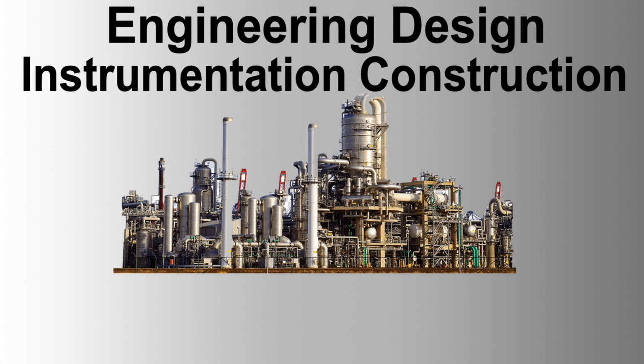Technical requirements. All instruments and their associated components shall be installed in accordance with all relevant drawings and data sheets. All instruments shall have individual connections to the process unless otherwise specified. No instrument shall be installed so that it depends for support upon the impulse lines unless so designed. The electrical connection. All instrumentation shall be accessible, i.e., from grade, permanent platform access walkway, or mobile platform.